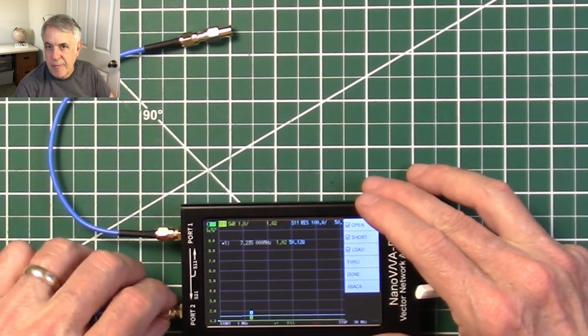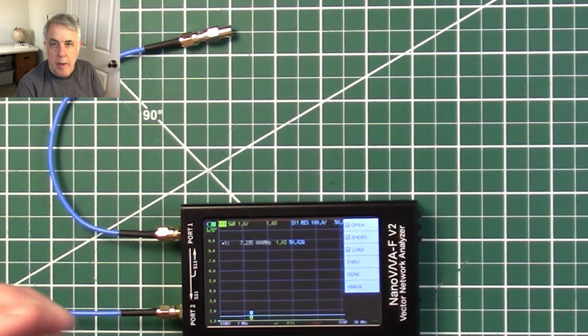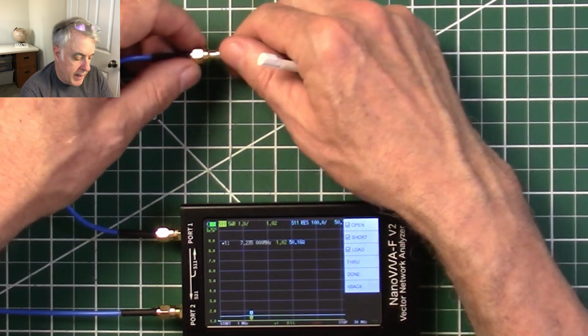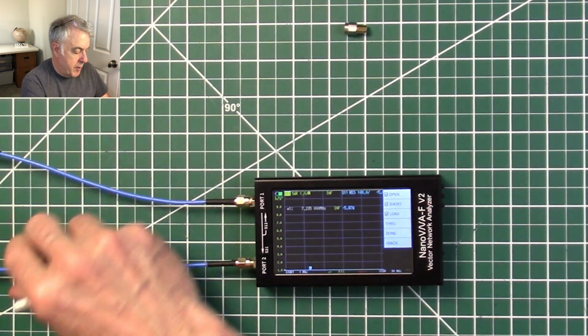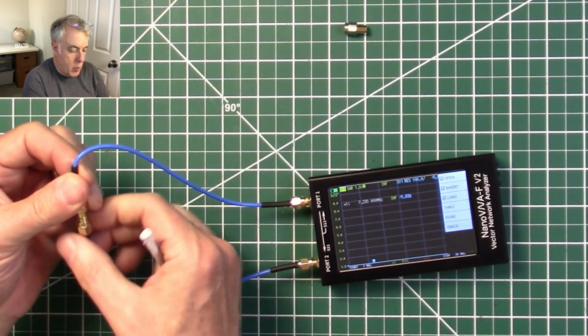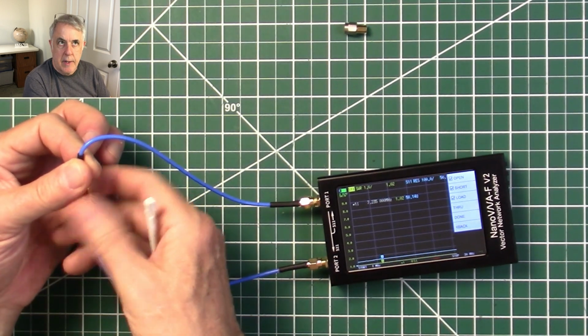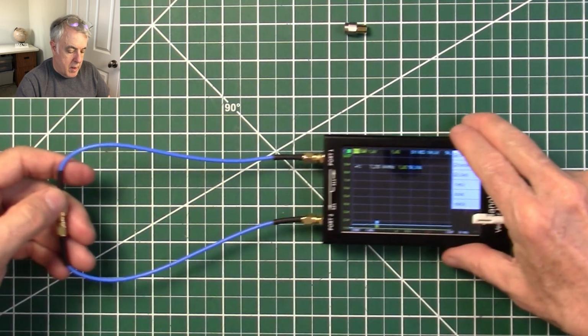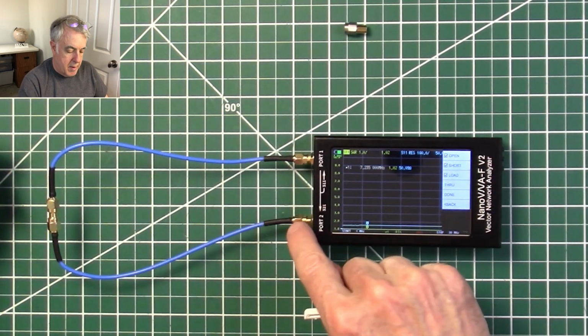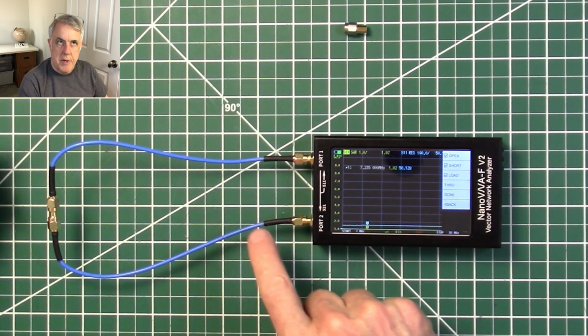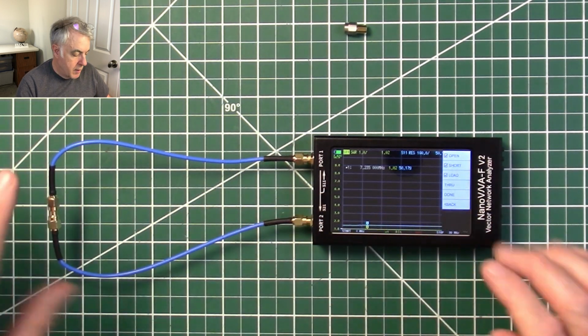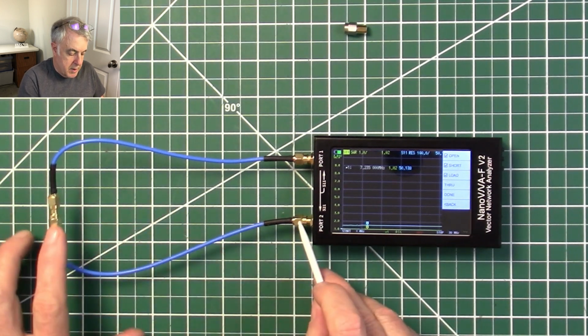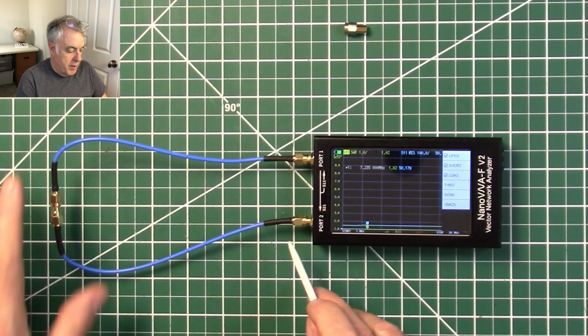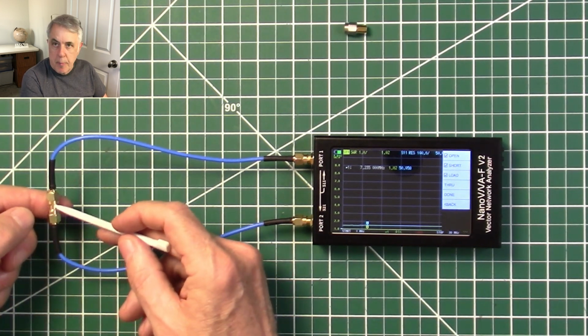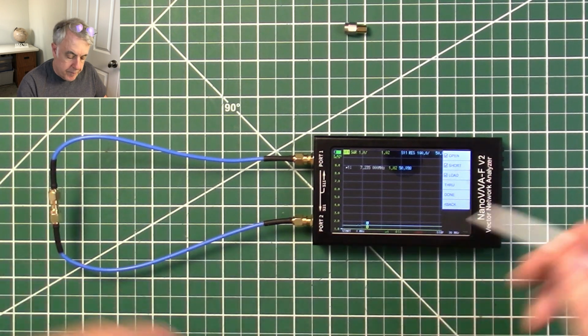I do it for every band that I've got stored here. I never know what I'm going to be testing next. But what it does, like if you've got a filter or a choke or whatever, and you want to test it, you'd send a signal out through the device under test back into it. That's the through. So what we're doing is calibrating for these cables, and any device we would put under test, we would insert it right here.